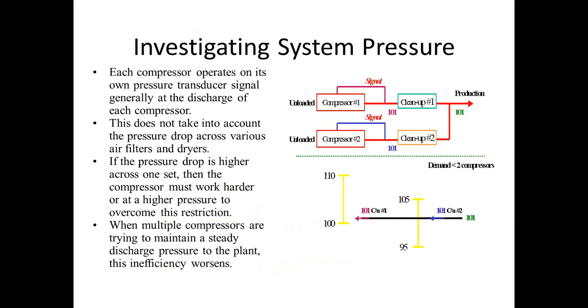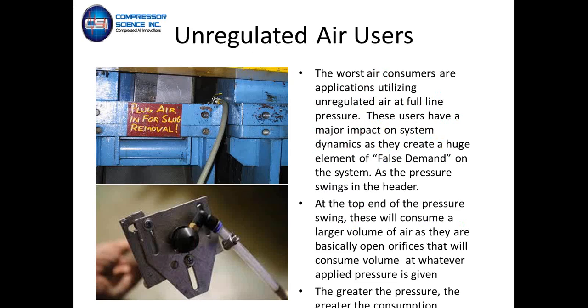When you've got multiple compressors set in a cascade type system like we just talked about, then you actually end up having to set your pressure bands at a much larger range in order to get your 95 or 100 out of the discharge of the compressor. You'll find a compressor, if it's running at 80-90% capacity, it's now got to run at full capacity to overcome that pressure loss just to get that 95 or 100 out of the discharge of the air treatment.